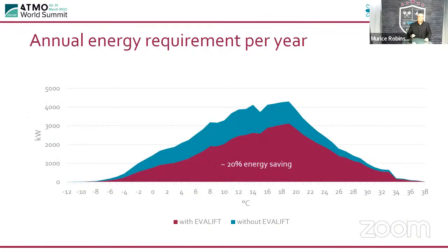So just to illustrate that, this is a graph of Frankfurt, which is where I am at the moment. This shows the outdoor ambient temperatures in hours per year. On the left-hand side, we've got the kilowatts of how much is used, and the temperature range at the bottom. You can see the average temperature is normally around 12 to 18 degrees, but that 18 to 20% energy saving is always there. So this illustrates that you can use a system summer, winter, it doesn't make a difference. You're still going to get the energy saving.